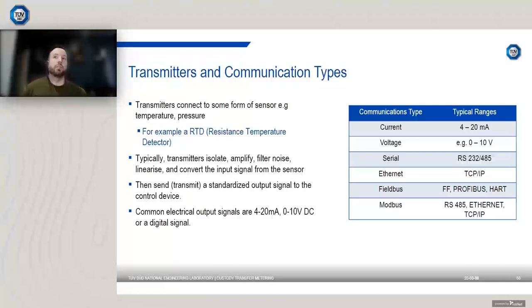Now, whether it's pressure, temperature, or even density, whatever you're measuring, there's usually some form of transmitter connected to the sensor. So what is the job of the transmitter? Well, it's taking the measurement from the sensor, so if it's a capacitance diaphragm pressure device, it's taking that and it's isolating, amplifying, and filtering out any electrical noise. But usually the most important thing it's doing is it's converting the input signal from that sensor to a standardized output. So it's taking that capacitance or it's taking that 4-wire resistance measurement and it's converting it to some other output signal. Now, commonly, things like 4 to 20 milliamp, 0 to 10 volts have been used, but digital signals are also popular now as well.